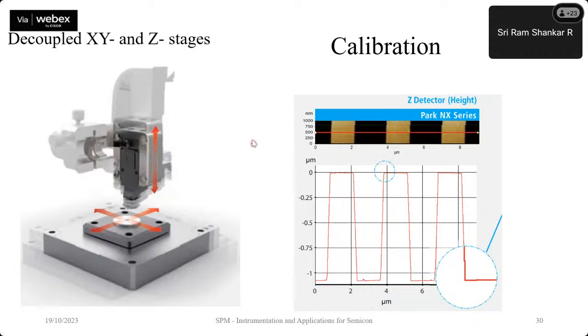In order to calibrate this sort of an instrument, we take a calibration grating, which are predefined patterns of known pitch and depth, and we look at the images we have measured to check whether such pitch and depth are being maintained or not. Accordingly, we can also infer the tip radius from such images.